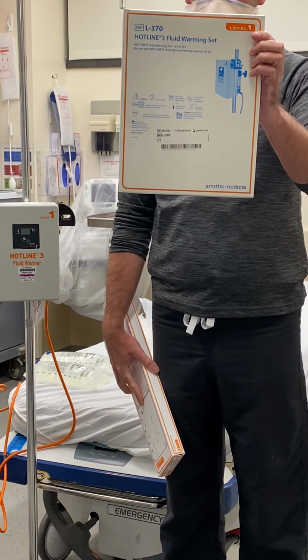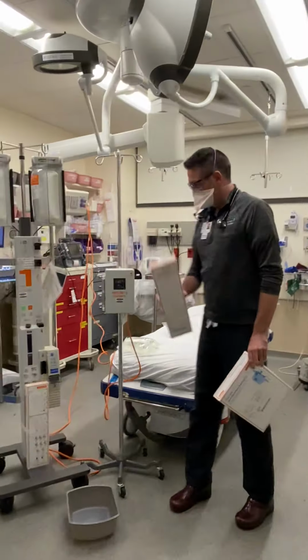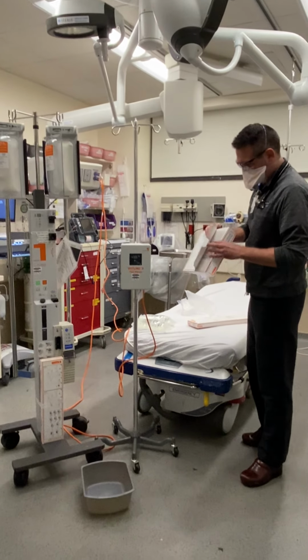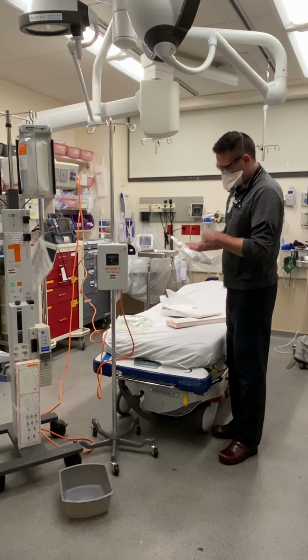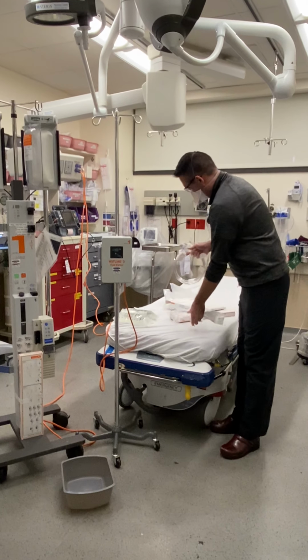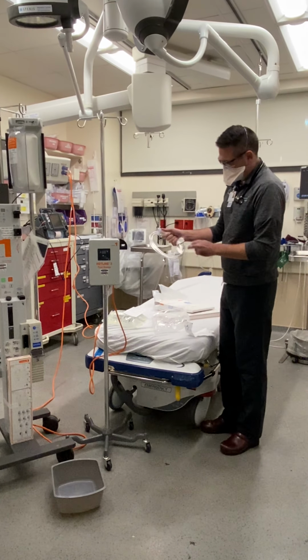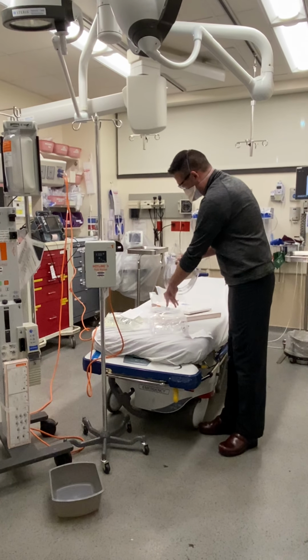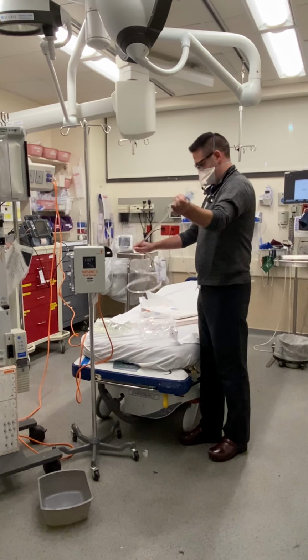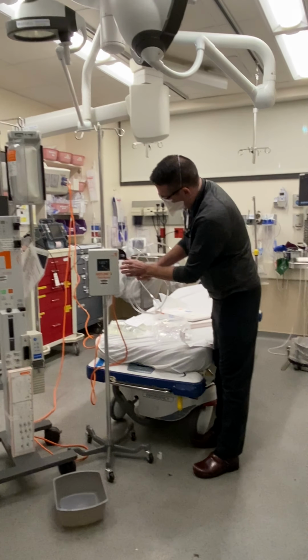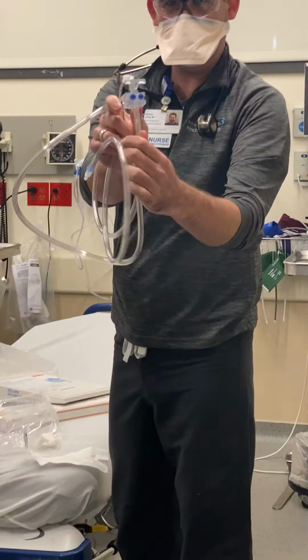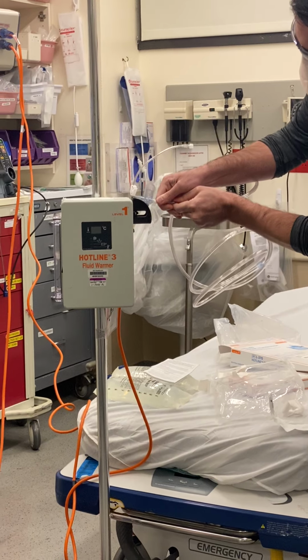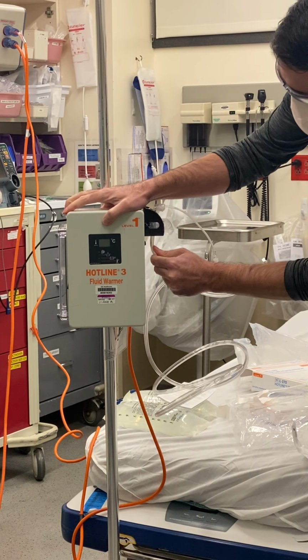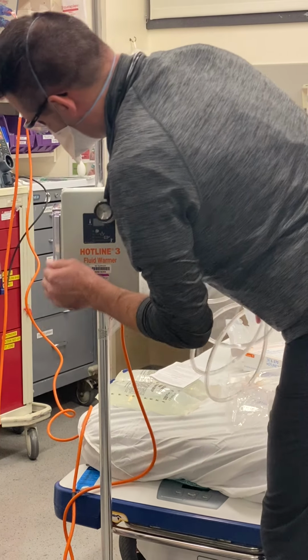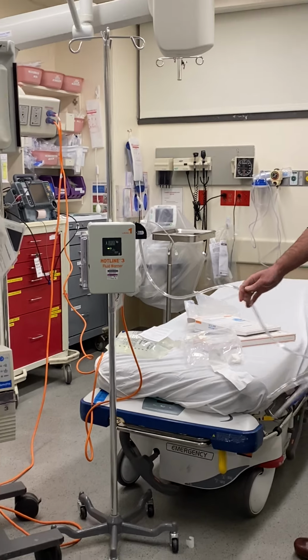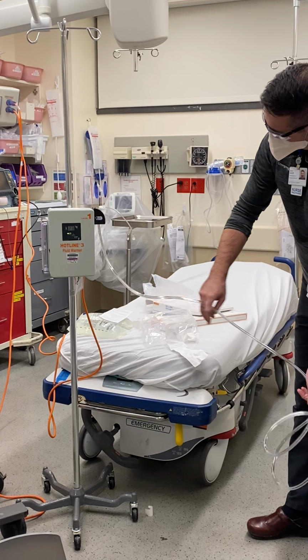This is for just the fluid warmer. This is for the level 1. Really quickly, to use the fluid warmer, you open up the cartridge. Typically, the patient should be monitored continuously by rectal temperature probe or esophageal temperature probe or something like this so that you don't overshoot. And what you need to do here is to get your cartridge in, and you take it by this little piece here and you just rest it in this groove and push it down into place. When you turn on the device, with its power over here, you will see fluid will rapidly start to fill through this tubing.